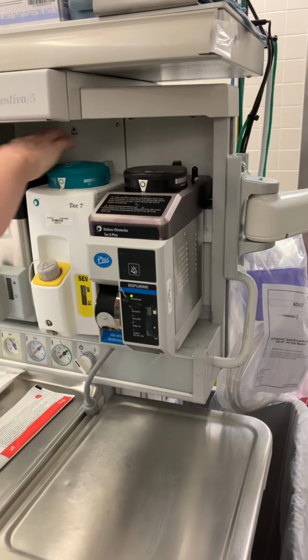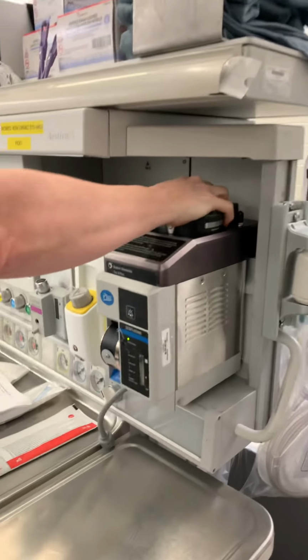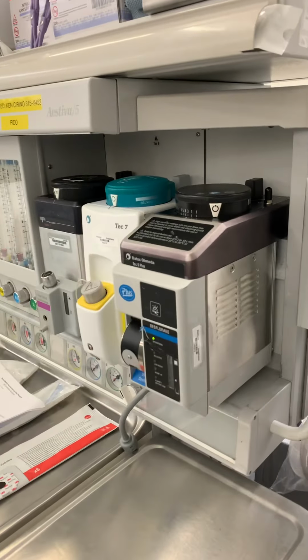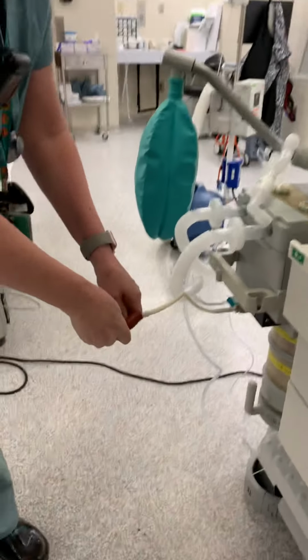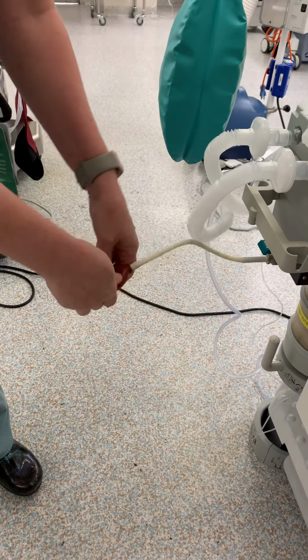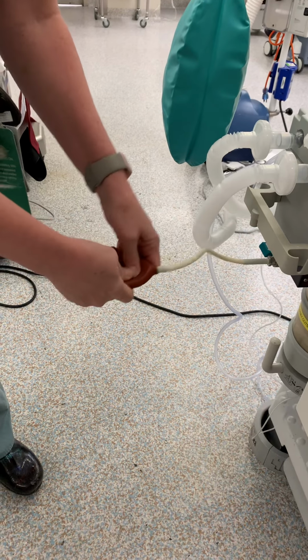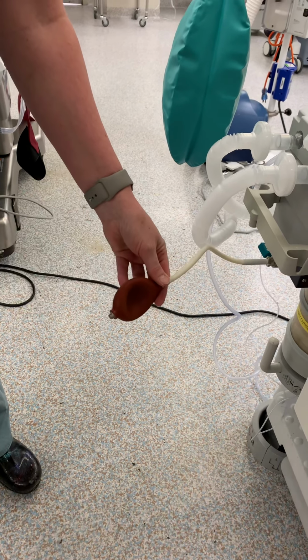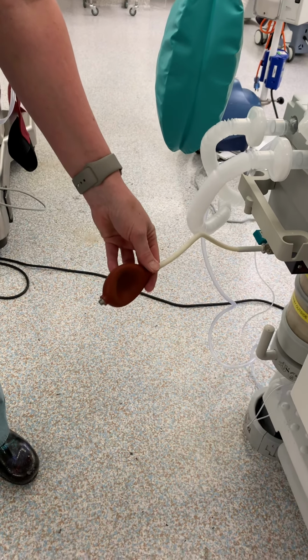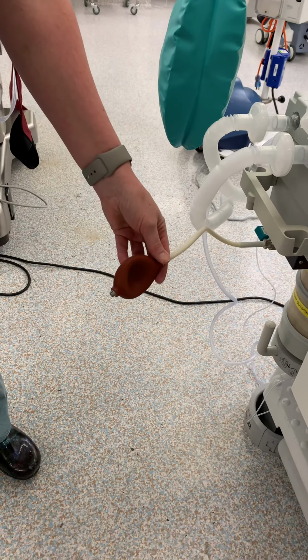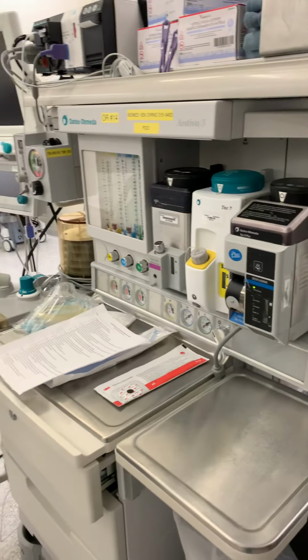sometimes this one turns on, sometimes it doesn't. There we go. The desflurane, again, the bulb filled back up, but we're just going to depress it and make sure that it maintains the negative pressure by remaining deflated. And again, this vaporizer has passed. So we are now done with this test.